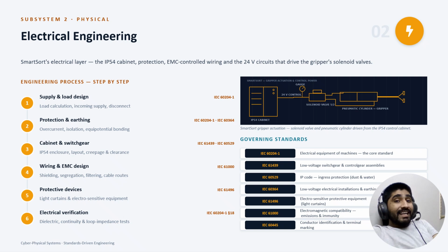Stage number 2, protection and earthing. IEC 60204 works with IEC 60364. Overcurrent protection is coordinated so the nearest device trips first. Every conductive path of the cell, frame, cabinet, conveyor, is bonded into one equipotential network, so a fault has a guaranteed low impedance path home and the breaker clears it in milliseconds.